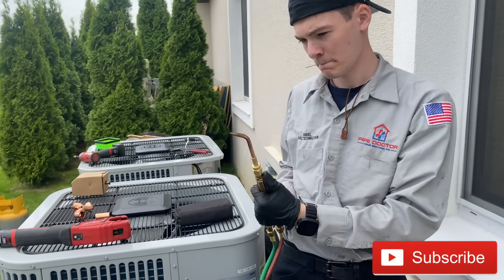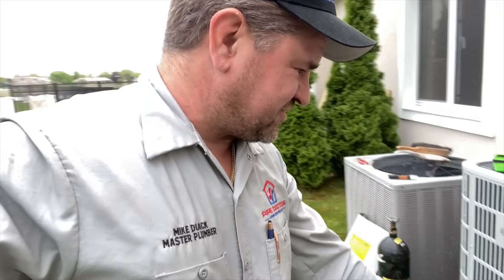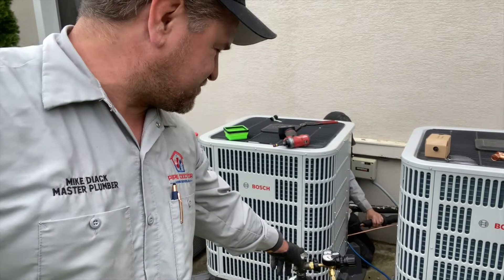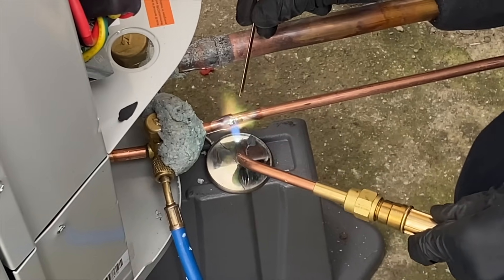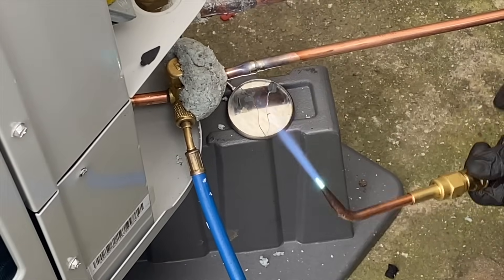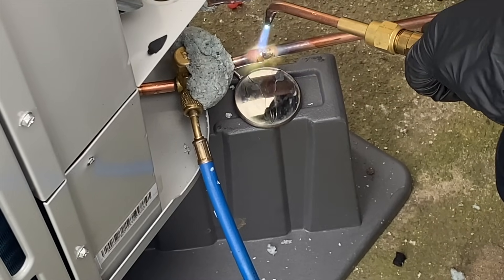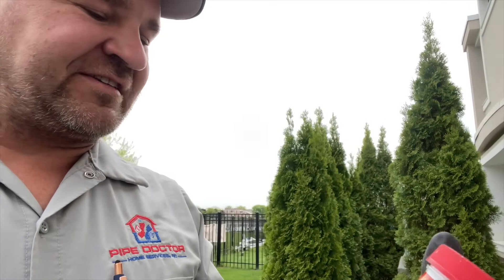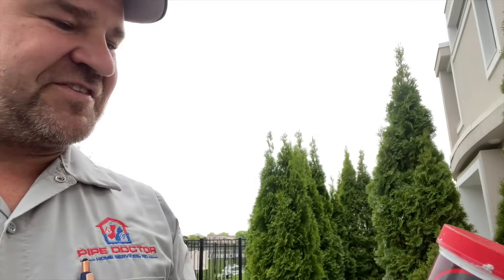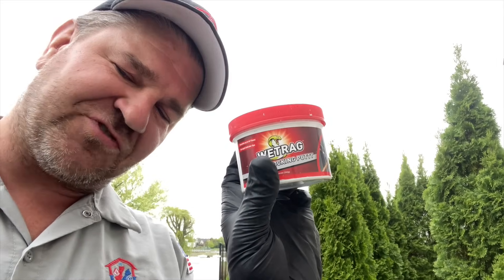You haven't seen Daniel using a brazing rig in a while. Daniel is flowing nitrogen through the system while he's brazing — smash that thumbs up if I caught you. On the left hand side covering the service valve, we're using a wet rag. Daniel is now brazing the three-eighths onto the king valve. The Wet Rag by Refrigeration Technologies is their heat blocking putty — a 12-ounce container, not that expensive and absolutely amazing. Not a sponsor, but they sent me some free gifts last year and I want to give them some love.